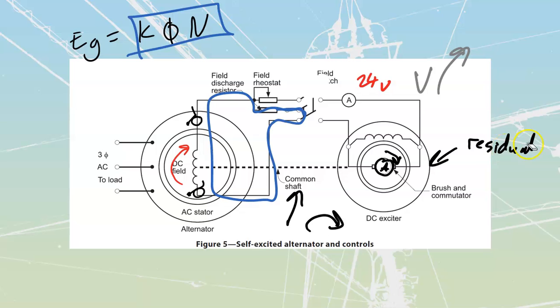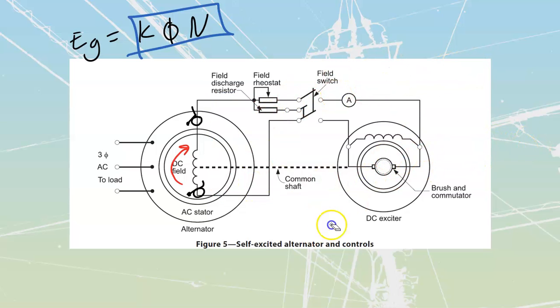There's a fair bit of maintenance involved with these when you look at them, because if you look at the components over here, I've got slip rings and brushes on this one, and brushes and commutators on that one. So that's four sets of brushes, for both my slip rings and for my commutator, that I have to maintain. I also have to maintain this field switch and my field discharge resistor over here as well, making sure these things don't get overheated from too long operation or anything like that.